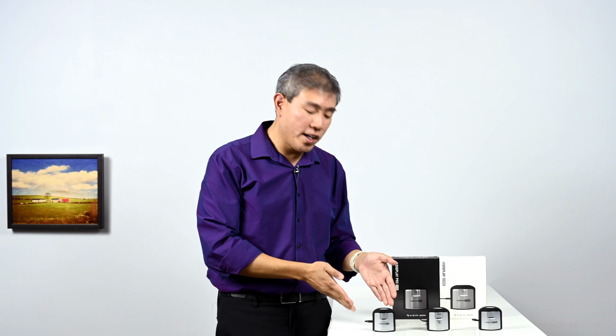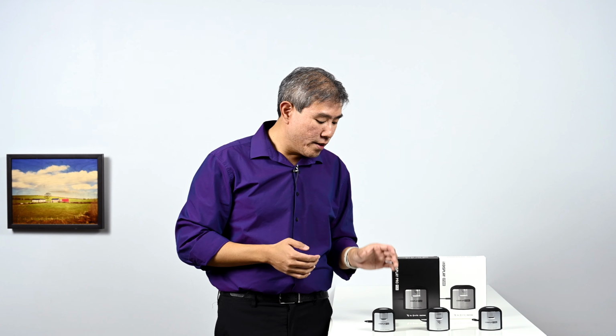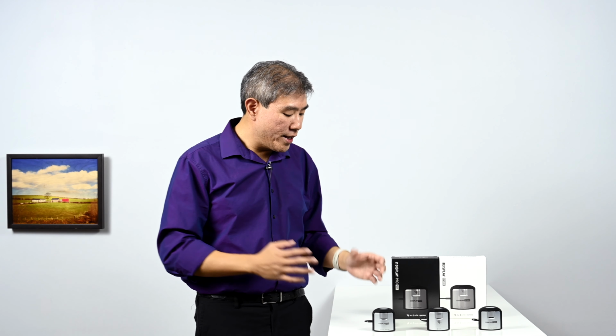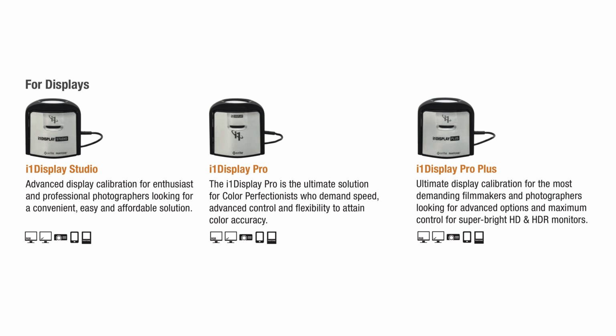Now, because these two use the same software, they can also do the same things. So what makes these two different? Well, this is the recently launched X-Rite i1Display Pro Plus. What makes this colorimeter great is that it can calibrate displays that are as bright as 2000 nits. What that means is that this colorimeter is going to be much more sensitive to different color ranges, different brightness ranges. This device should be one of the best colorimeters out there to calibrate any display.